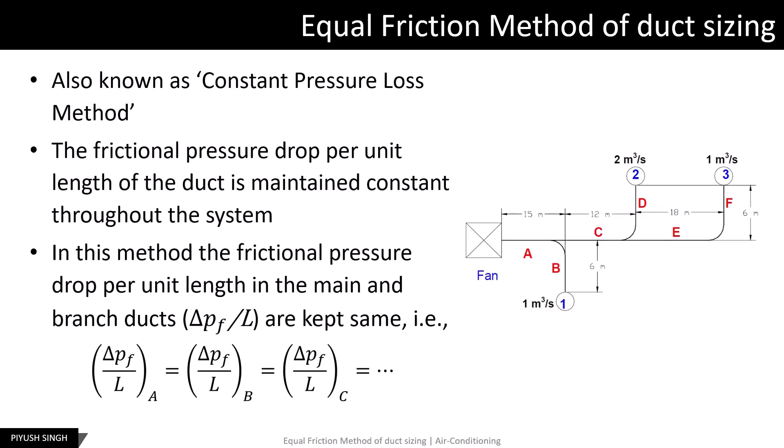The Equal Friction method of duct sizing, also known as the Constant Pressure Loss method, is one of the most popular methods of duct sizing in simple duct systems. The frictional pressure drop per unit length in this method is assumed to be constant throughout the system. Taking the example of the duct system shown in the figure, while sizing the ducts, the frictional pressure drop per unit length in ducts A, B, C, D, E, and F are assumed to be equal.